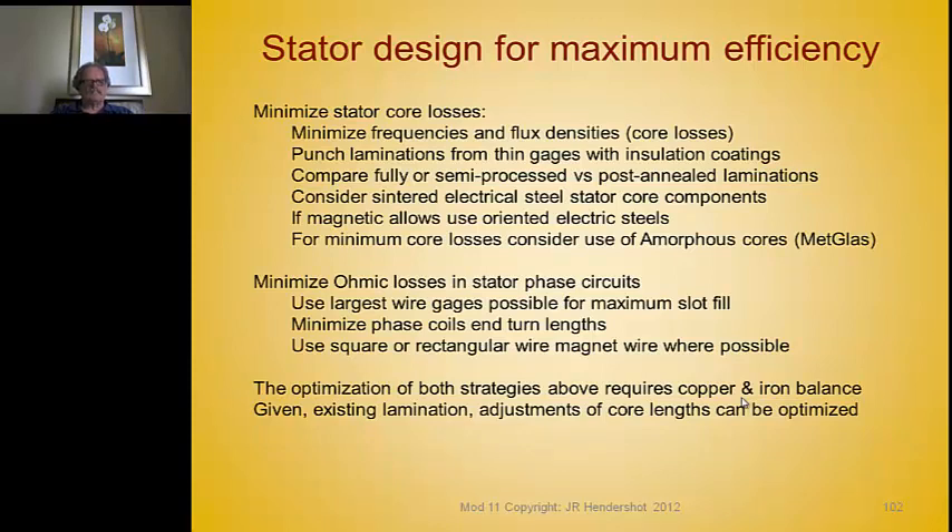Minimize ohmic losses in the stator phase circuits. Use the largest wire diameter possible with maximum slot fill, and minimize phase coil end turn lengths — keep the coils short. These are the three main strategies to convert standard grid induction motors to high efficiency: use better lamination materials with insulated coatings, achieve higher slot fills, and minimize end turn height. Those are the three strategies used to go to premium efficiency motors.